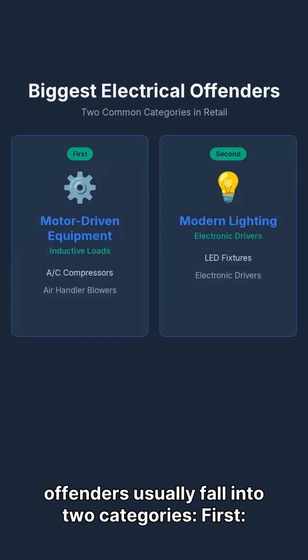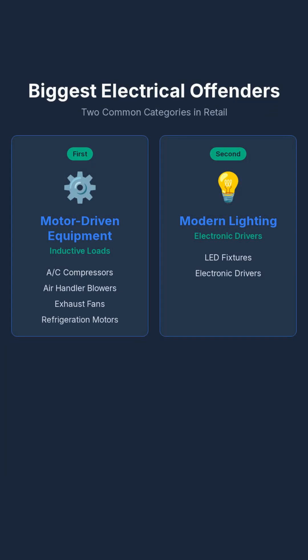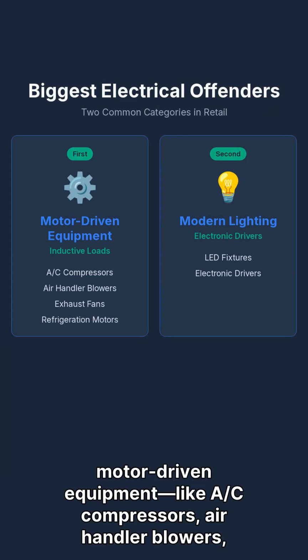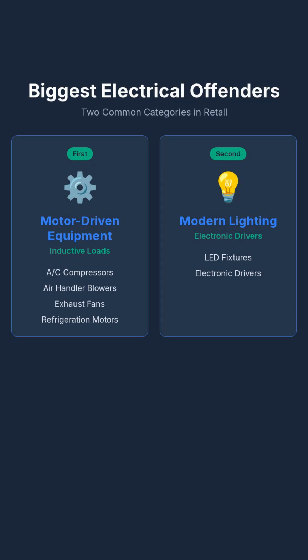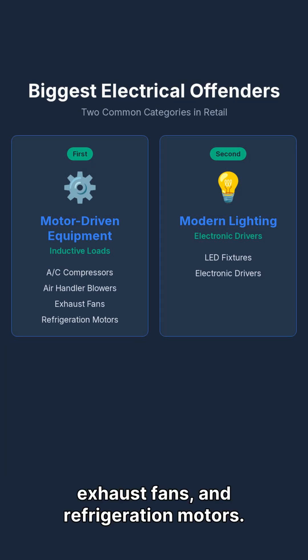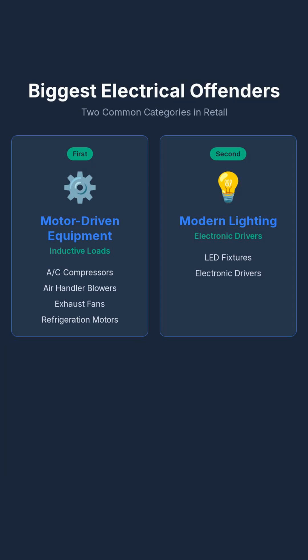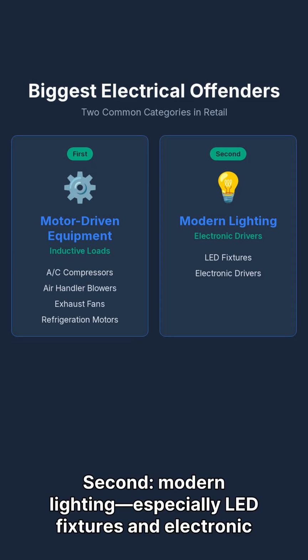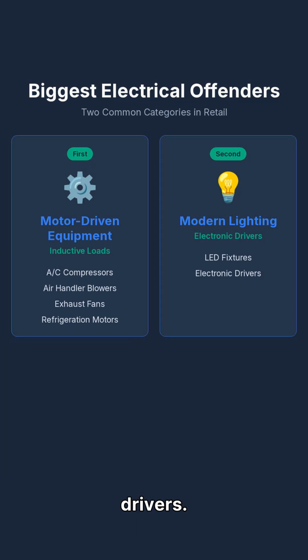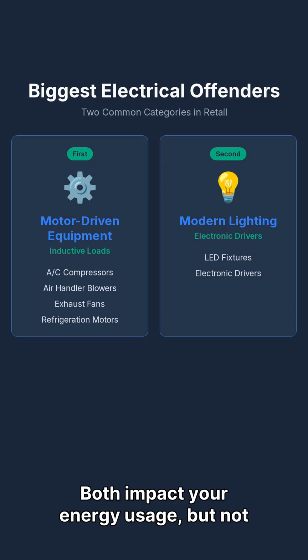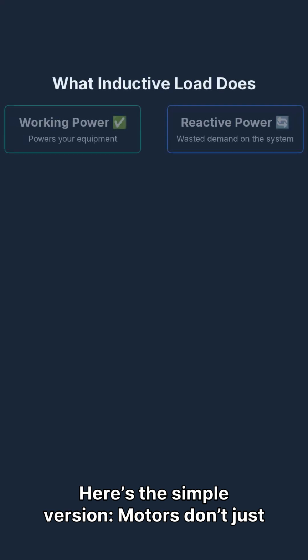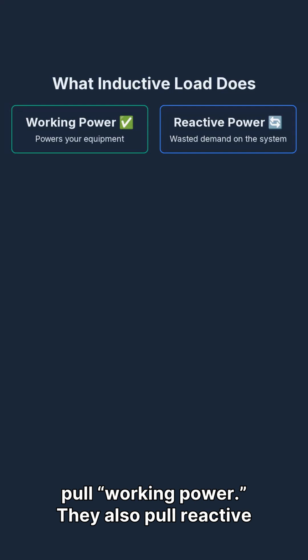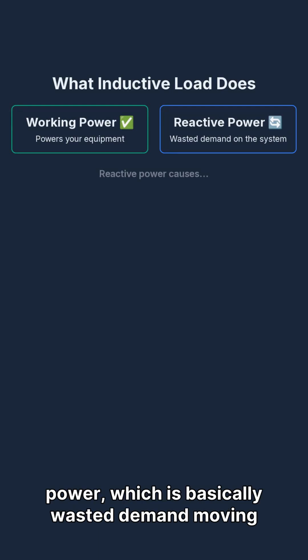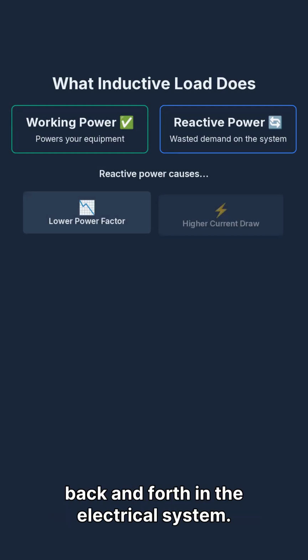In a retail environment, your biggest electrical offenders usually fall into two categories. First, motor-driven equipment, like AC compressors, air handler blowers, exhaust fans, and refrigeration motors. These are called inductive loads. Second, modern lighting, especially LED fixtures and electronic drivers. Both impact your energy usage, but not always in ways you can see. Here's the simple version. Motors don't just pull working power. They also pull reactive power, which is basically wasted demand moving back and forth in the electrical system.